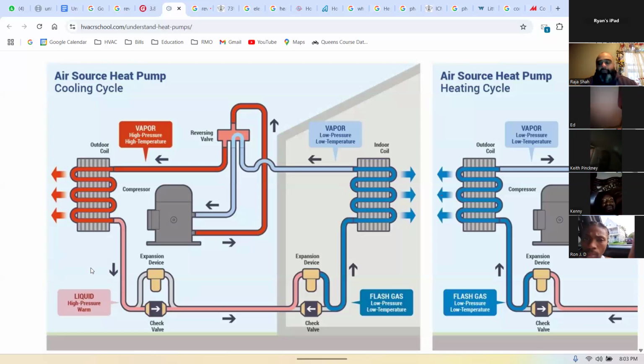So what do we read when I put on my gauges for us when we're on the job, what are we reading on the high side? We're reading the liquid refrigerant, we're reading what temperature it is, we're reading the saturation temperature. That's the point where you're going to go from the vapor to liquid.